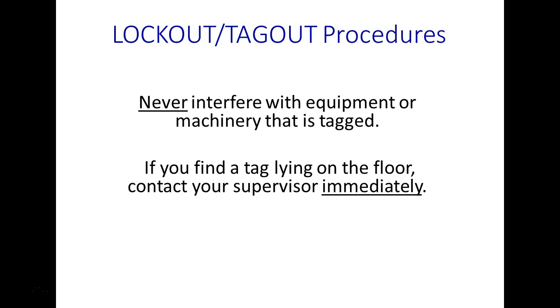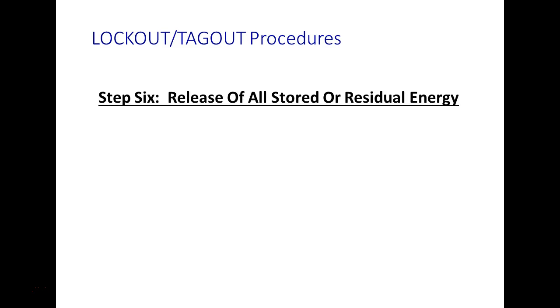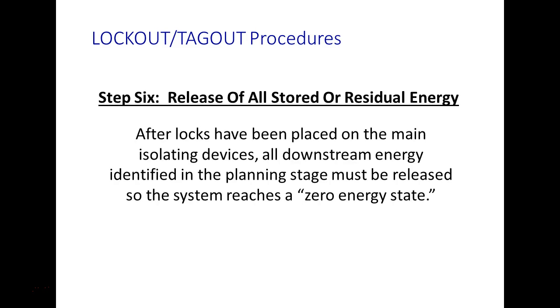When we worked out there, we had tags. We had paper tags. Release all stored energy and residual energy after the lock is placed on the main isolating device, all downstream energy. Downstream means between you and the disconnect, right? Between you and the machine. Release all downstream energy until the system reaches a zero energy state.